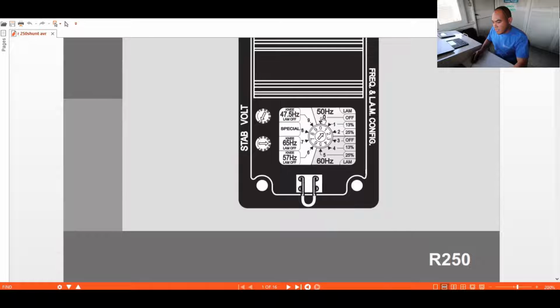For 50 to 60, we have the LAM off, the LAM for 13%, and the LAM for 25%. So this is at 50 hertz. For the 60, you have the LAM off, and you also have the 13 and 25 LAM percentage. Here we have the 65 and 57 if you need this for your over and under frequency. You have the special number 8, and number 9 for 47 and 47.5 hertz, LAM off. So this is all 65, 57, all LAM off.